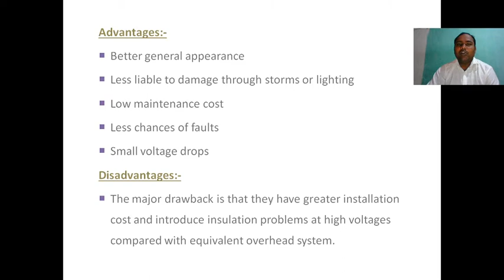Disadvantages. The major drawback is that they have greater installation cost and introduce insulation problems at high voltages compared with the equivalent overhead system. If any fault occurs in underground cables, recognition of the fault is very difficult because they are located underground. Also, from the cost point of view, underground cables cost more than the overhead line system because there are more layers, meaning more insulation around the conductors.